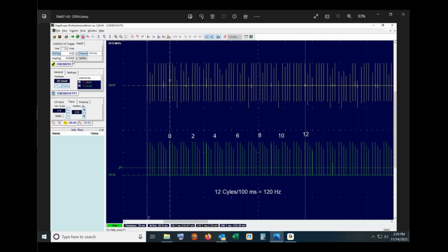By doing that, I put the cursors exactly 100 milliseconds apart, and then I counted this variation in the amplitude of the external trigger pulse. And you can see there are exactly 12 cycles of this variation. 12 divided by 100 milliseconds works out to 120 hertz, which is exactly twice the 60 hertz line frequency. So that tells us that somehow our ultrasonic pulser receiver is picking up twice the line frequency. That almost diagnoses what needs to be done to repair it, which of course we won't do.